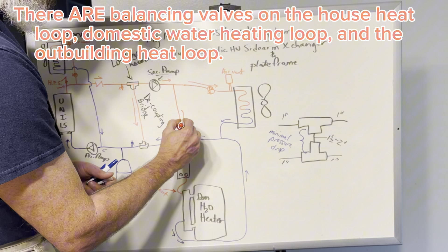And practice what you preach. So my plate frame heat exchanger is first. It goes into the heat exchanger, out of the plate frame heat exchanger, into the sidearm, out of the sidearm heat exchanger, and comes back. So if this is not being used, if I'm not heating my house, water's going like this, through the plate frame heat exchanger, through the sidearm heat exchanger, and back like that.